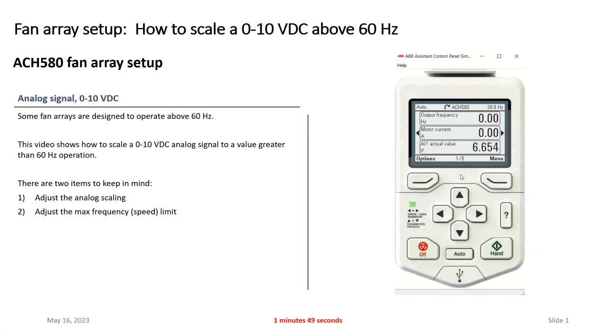Hi, Tim Skell here, ABB HVAC application engineering. Today we're going to take a look at starting up an ACH 580 with a fan array application. This particular fan array application operates at 72 hertz maximum speed, and they want to use a 0 to 10 volt signal to control that 0 to 72 hertz.